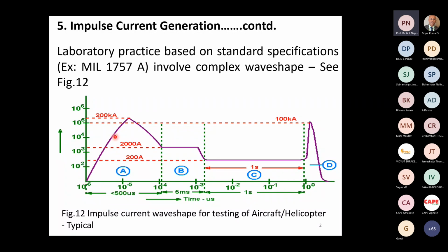So you'll see that this current is 200 kiloamperes. That's the worst possible lightning stroke. This is what's called the follow-up current. This is only 2 kiloamperes. Please remember, this is a logarithmic scale. This is 200 kiloamperes for scale. This is only 2 kiloamperes lasting for 5 milliseconds. That means 5,000 microseconds. Please see, the time scale is also logarithmic. So this is only about 500 microseconds, not more than that. This is 5,000 microseconds. And then we have got the 200 amperes for a full 1 second.